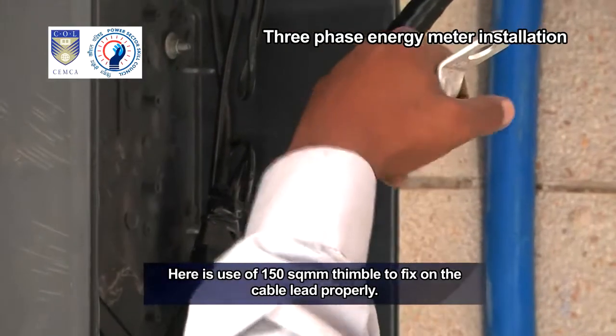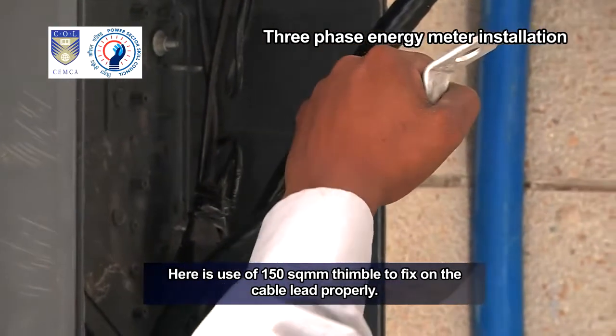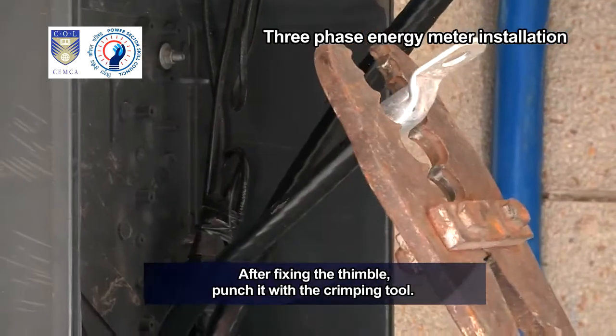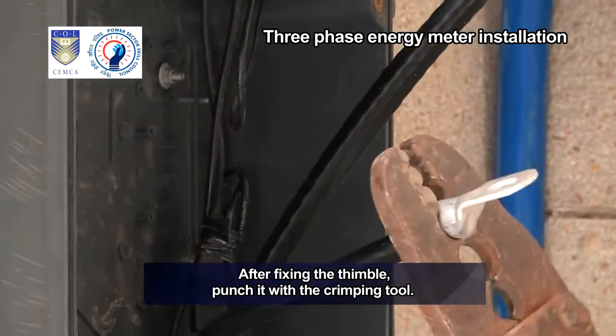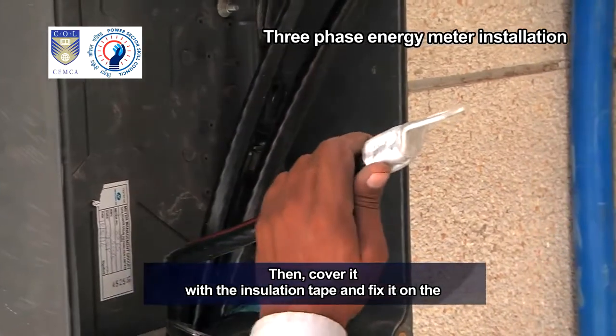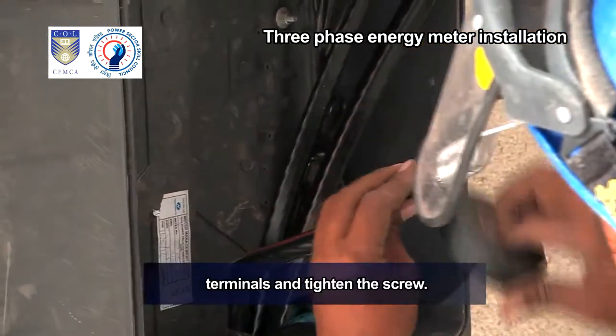Here is use of 150 square mm thimble to fix on the cable lead properly. After fixing the thimble, punch it with the crimping tool. Then cover it with insulation tape and fix it on the terminals and tighten the screw.